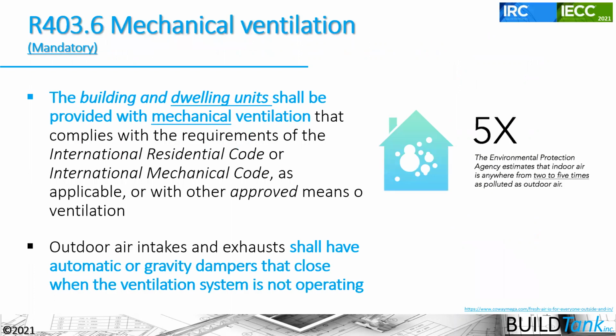Now, mechanical ventilation is described in the IRC and the IECC in kind of the same way. Starting with the IECC, it says the building and dwelling unit shall provide mechanical ventilation. Now, the underlined portions here are new to the 2021 IECC. So we're getting down to a dwelling unit level in multifamily buildings. And we're talking now about mechanical ventilation. So we're not talking about just opening a window and having random airflow in and out of our houses. Just because I open a window doesn't mean that air from the outside is going to come into the house at all. So we need that mechanical component as well.